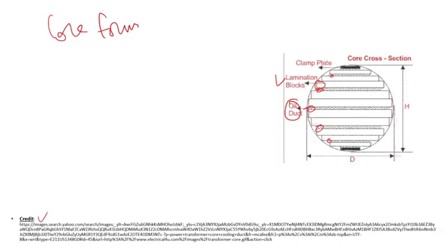And if you overheat oil and then you overheat paper, they're going to start releasing gases and other things. Pressure will go up, and all that gas, that pressure needs to get out. And if somehow there is a leak or oxygen makes it inside, air basically makes it inside, now you have a recipe for fire basically. So that's why you want to control it.